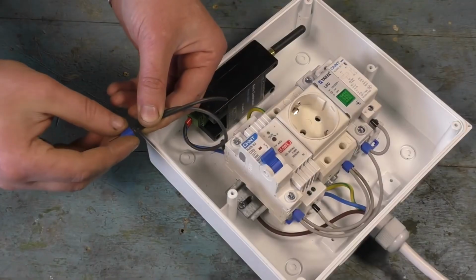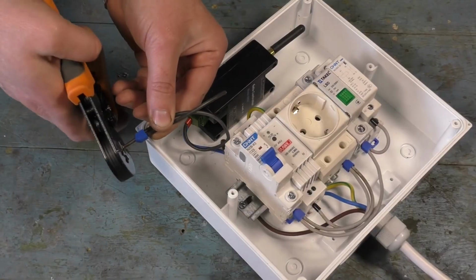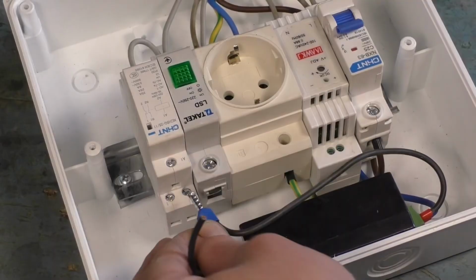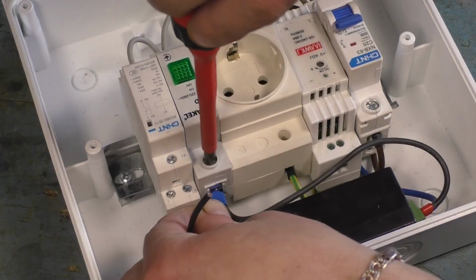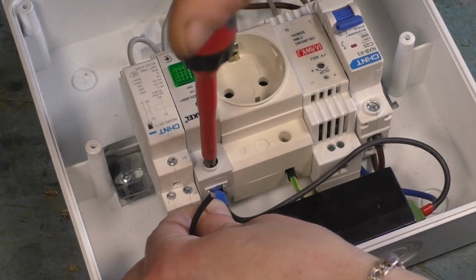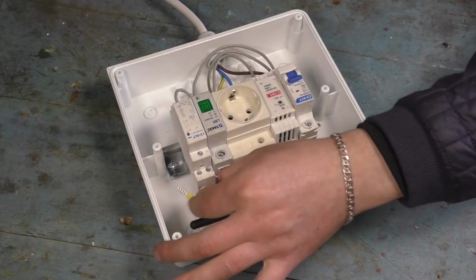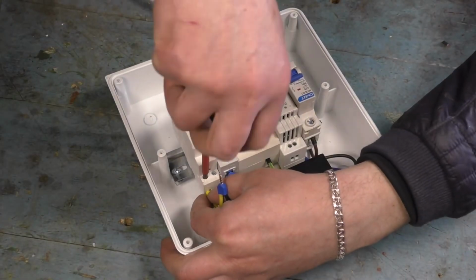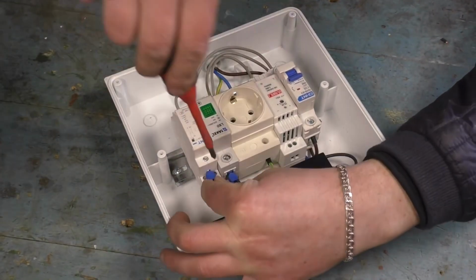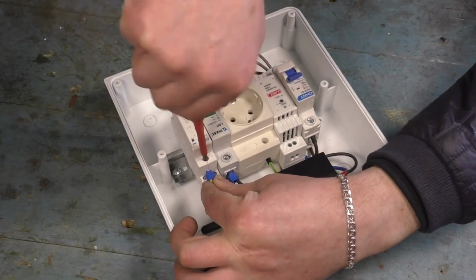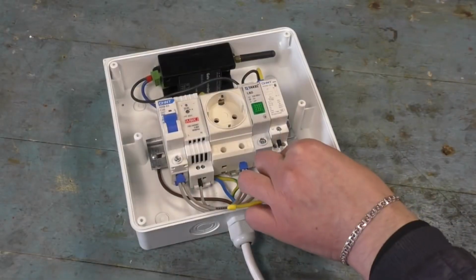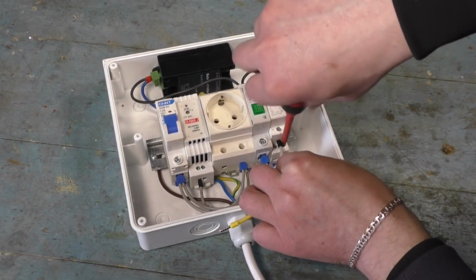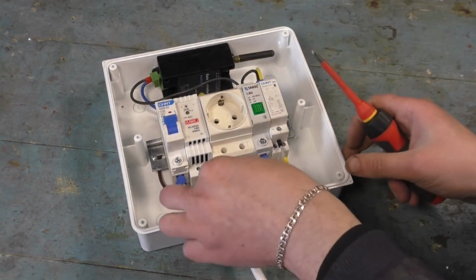You need to add a jumper to the wire coming from the NO contact. After that, connect it to the signal lamp. You need to add another piece of wire to the jumper and connect all of this to the contactor. One wire is connected to the coil and the other to the normally open contact of the relay. The other terminal of the relay's normally open contact is connected to the socket.